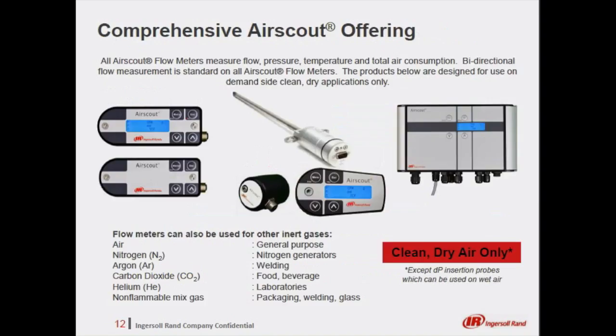The Airscout flow meters consist of a comprehensive product line with capabilities to measure multiple parameters including the flow, pressure, and temperature, as well as that total air consumption. The Airscout product line is designed for use with inert gases including air, nitrogen, argon, carbon dioxide, helium, and other non-flammable mixtures. Product technologies are also available for both the wet, untreated air of the supply side, as well as the clean, dry air of the demand side.